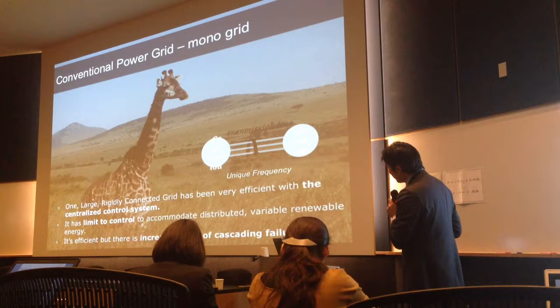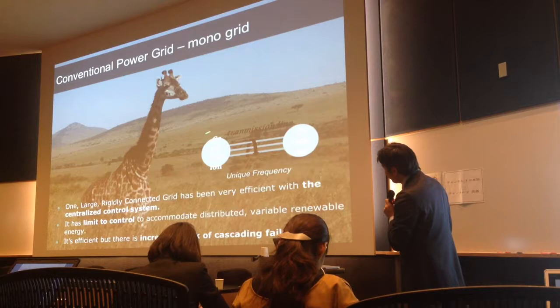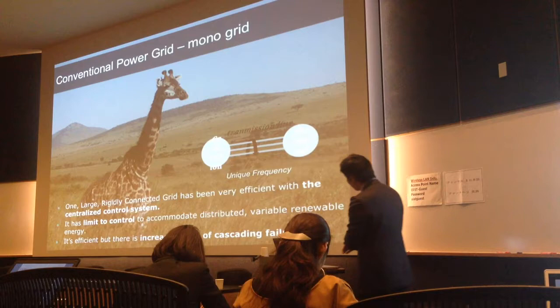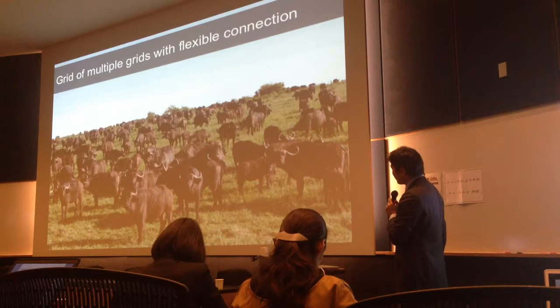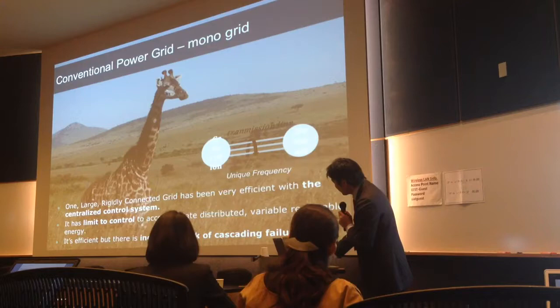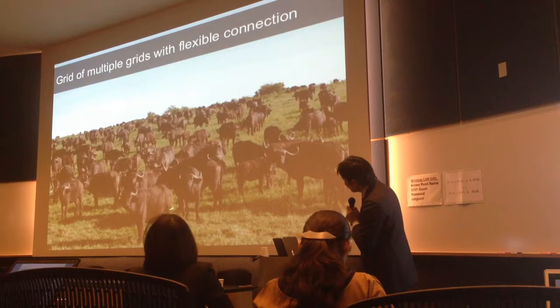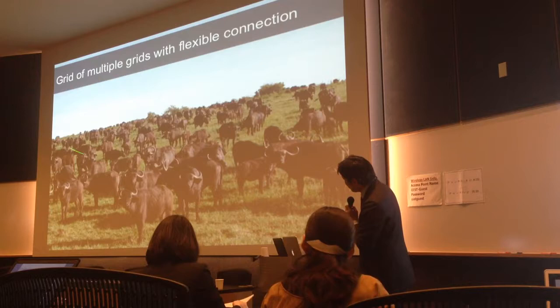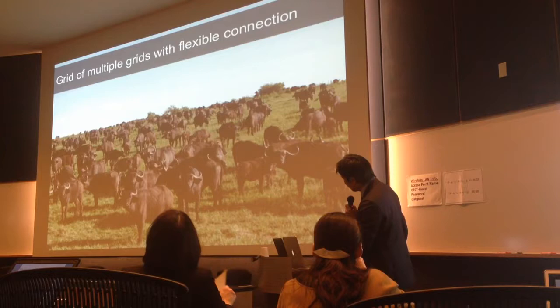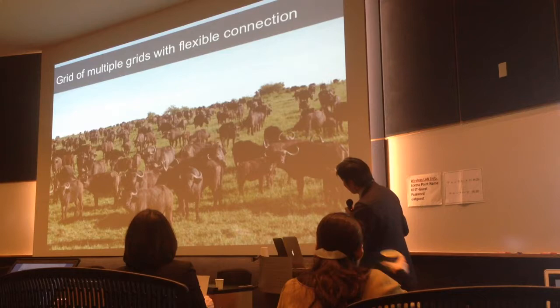The problem is that at each moment, generation and demand must be balanced. If you lose the balance, cascading failure will occur. The solution is a distributed grid architecture. Compared to the conventional grid, each individual grid cell will be somewhat weaker, but if one grid fails, the rest of the grid remains safe. We believe this has good compatibility with renewable resources.